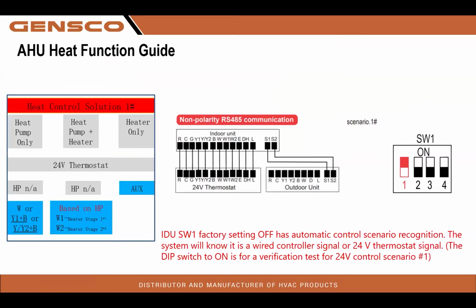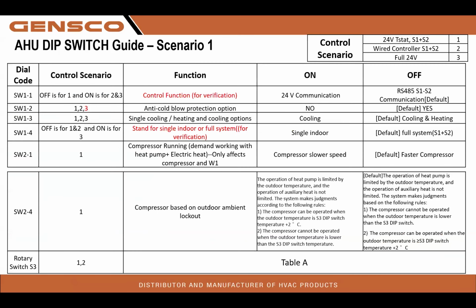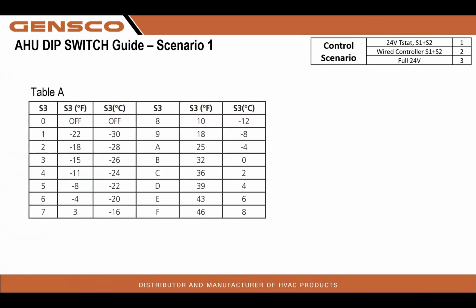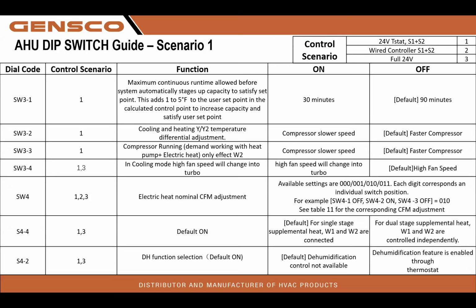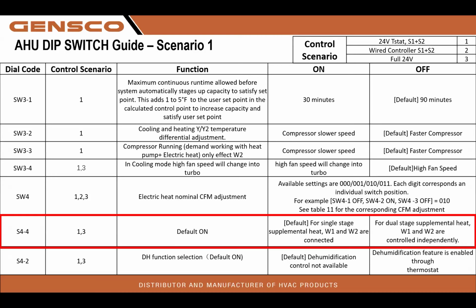Air handler unit heat function guide. Indoor unit SW1 factory setting is off, has automatic control scenario recognition. The system will know it is wired control signal versus 24-volt signal with dip switch SW1 in the on position, auto recognize. Make sure you look into your install manual for the exact dip switch functions and settings. Like I said, right out of the box, you don't need to set any at all. We're not going to spend a whole lot of time on dip switches. There's SW4-4, control scenario 1-3, default on. For single stage supplemental heat, W1, W2 are connected. For dual stage supplemental heat, W1, W2 are controlled independently with SW4-4, either on or off.